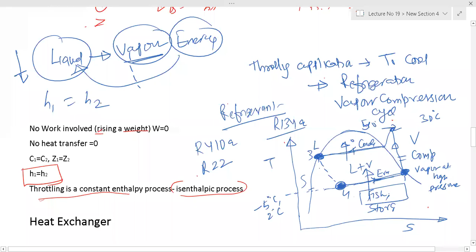So in H2 you have two phases, liquid plus vapor, and in H1 you have only liquid. So some part of this liquid will be converted into vapor, and because there is no heat interaction and no work interaction, this vapor will form. That requires some energy, so this vapor will take the energy of this liquid, and finally this liquid temperature will go down. So here a mixture of refrigerant vapor plus liquid will form, and that will be at very low pressure and low temperature. Gas cannot be throttled because gas is not liquid, and the enthalpy of a gas is a function of temperature only. So there is no liquid part here. So you cannot throttle gas.